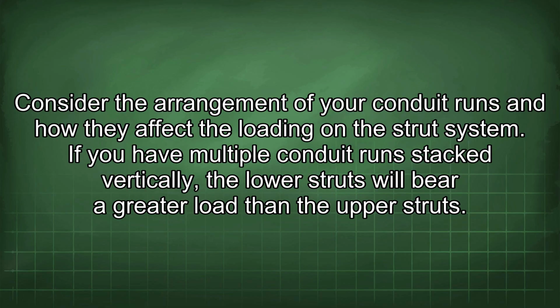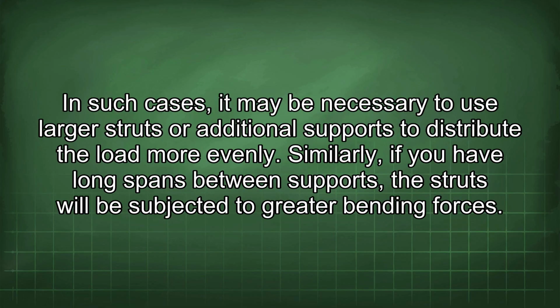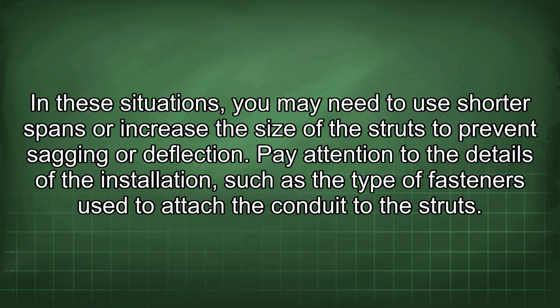Consider the arrangement of your conduit runs and how they affect the loading on the strut system. If you have multiple conduit runs stacked vertically, the lower struts will bear a greater load than the upper struts. In such cases, it may be necessary to use larger struts or additional supports to distribute the load more evenly. Similarly, if you have long spans between supports, the struts will be subjected to greater bending forces. In these situations, you may need to use shorter spans or increase the size of the struts to prevent sagging or deflection.